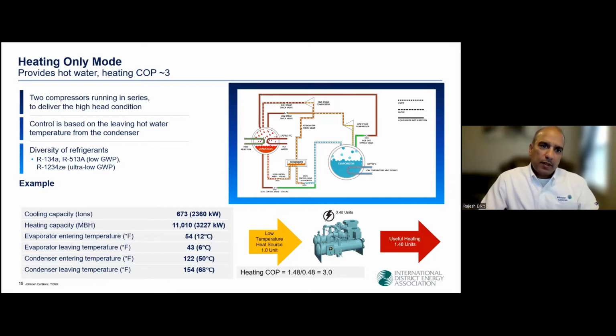So to summarize the heating only mode, we are feeding one unit of some sort of a low temperature heat source in the evaporator and using 0.48 units of energy to do the compressor work. So the 1 plus 0.48 equal to 1.48 units of heat is what is available from the condenser. And therefore the heating COP is 3, which is 3 times more efficient than a fossil fuel fired boiler.